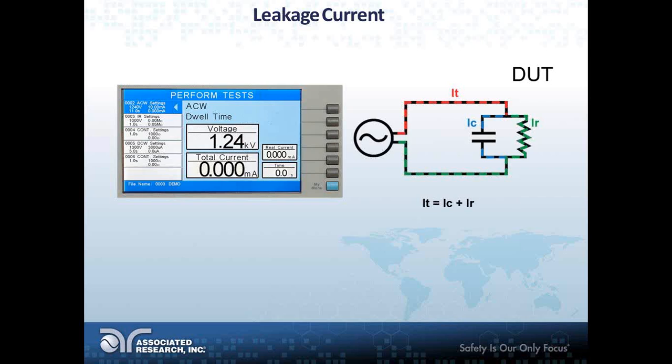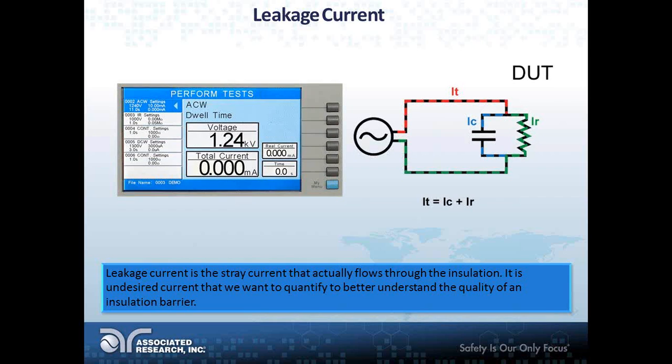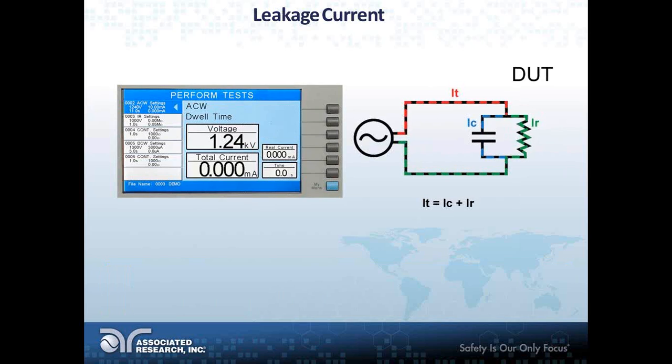Next, leakage current. Well, all electronic products have leakage current to some extent. Some devices have leakage current values that are very small and hard to detect, but some others have higher leakage. And this leakage current is a result of the product running at its normal input voltage.